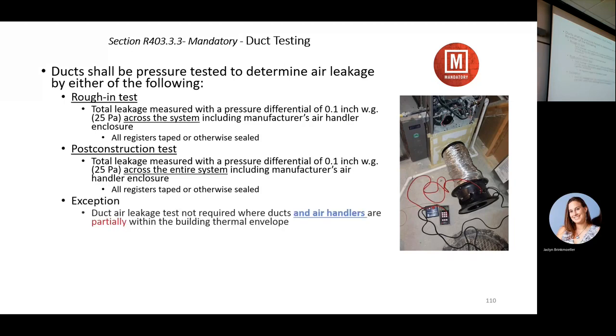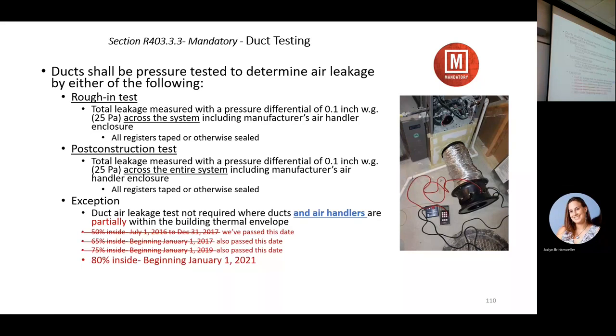And I'm not going to read through all this because I just mentioned it to you. We started out when we first had this state amendment that if you have 50% or more of the duct outside the envelope, you had to test. And what we've got up to now is you can only have 20% outside, or 80% has to be inside the envelope, before you have to test. So you can only have less than 20% outside the envelope. So you might be able to run some runs to a bonus room or something like that and not have to test, but it's very rare. And then there has to be a written report.